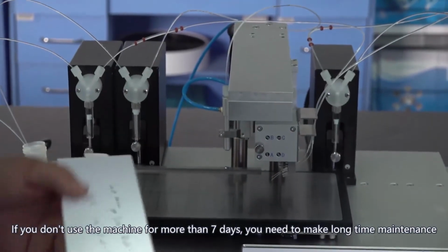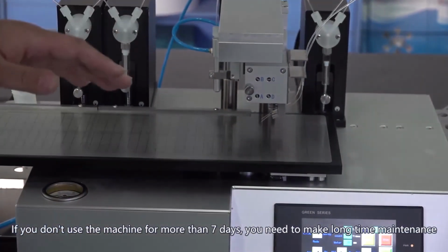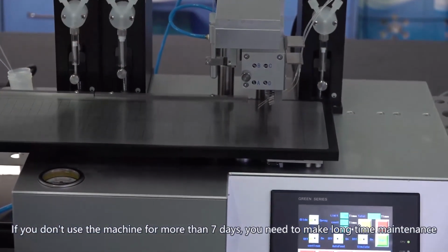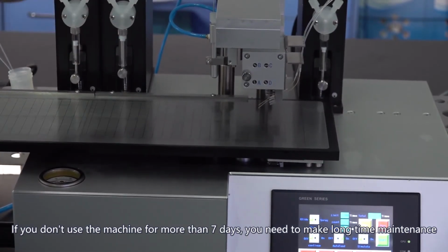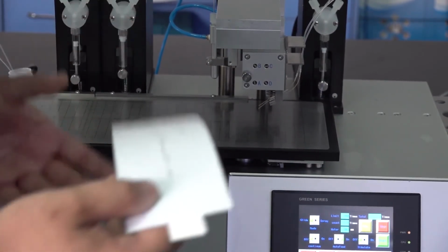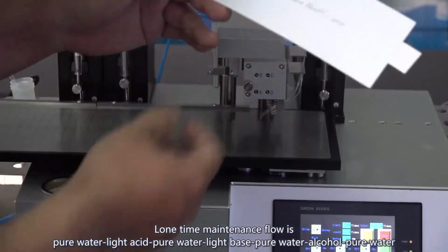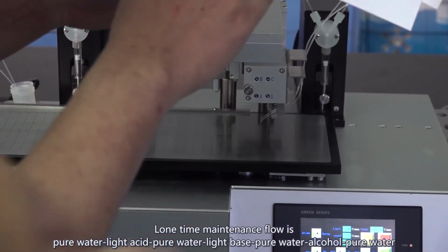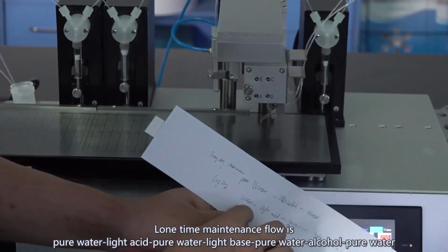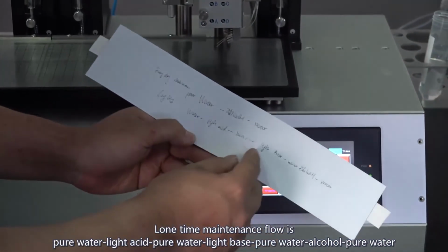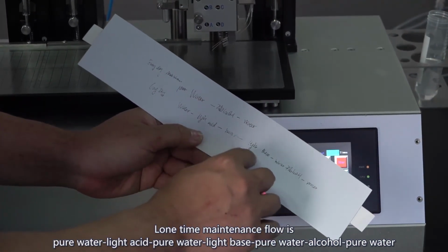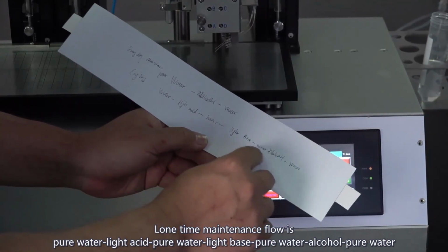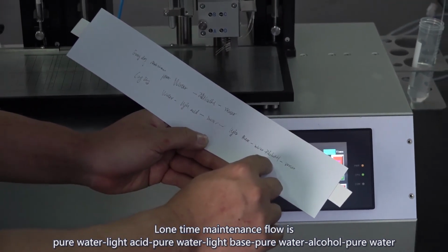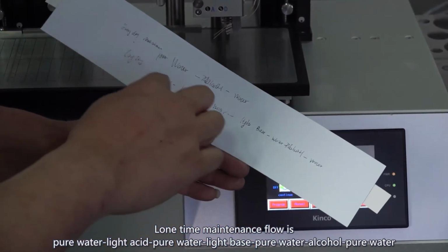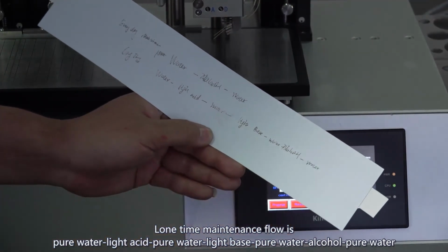If you don't use these machines for more than 7 days, you need to do a long-time maintenance before you stop. The process of long-time maintenance is the water, light acid, and the water, light base, and the water, 75% alcohol, and the water. This is the process for the long-time maintenance.